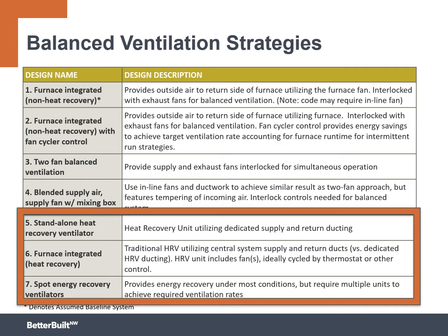When we think and talk about strategies used across the country to provide balanced ventilation, almost everything can fit into 7 different categories. We can talk about integrating in with our furnace, meaning we use an exhaust fan or multiple fans to exhaust air out of the house, and then we supply the same amount of air in, and we pipe that into our central air handler, and we try to make sure that those are balanced flows. We can do that continuously, which is option number 1, or we can do it intermittently, which is option number 2. In that case, we may use a tool called a fan cycler, a type of controller that prioritizes opening the damper for ventilation when there's a call for heating or cooling.